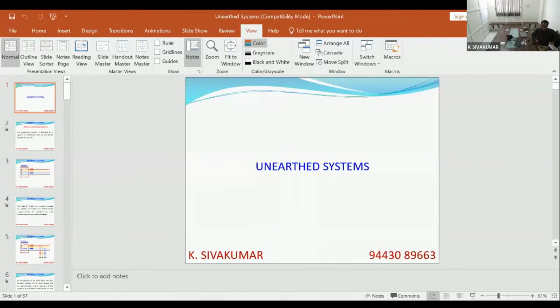So maybe in a subsequent presentation, I will discuss selection of lightning arresters. But to answer your question, for an unearthed system, if you want to provide a lightning arrester, the rated voltage is the highest system voltage into the ground fault factor. The ground fault factor for an unearthed system is 1.732. So suppose you want to install a surge arrester for an 11 kV system, the rated voltage is 12 into 1.732, somewhere around 20 kV. You have to put a 20 kV arrester for an 11 kV system. That is what the standard says.